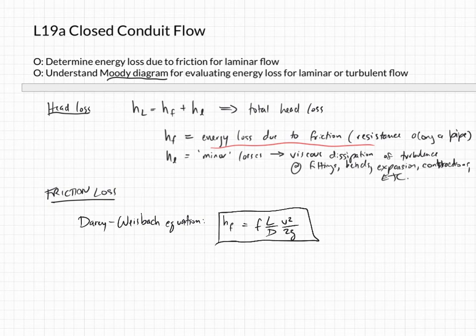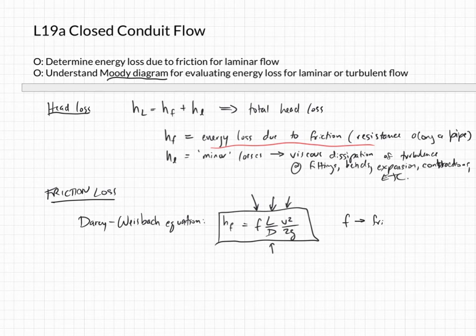This Darcy-Weisbach equation tells you how much energy you're going to lose for a given length of pipe of a certain diameter with the velocity flowing at a certain rate. This F is a friction factor and it depends on a lot of different things — that's kind of what we're going to be spending the rest of this class talking about. It's usually on the order of 1/50 or 1/100, so something like 0.01 or 0.02. I don't think you'll ever get higher than about 0.03.